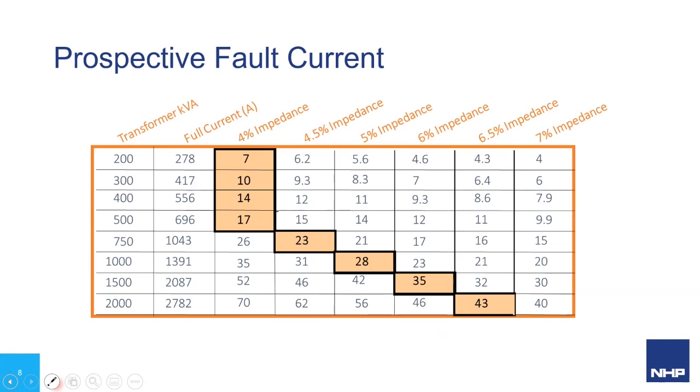The table shown here illustrates the possibilities of prospective fault current given an upstream low voltage transformer size, assuming an unlimited upstream supply and an internal build characteristic of the supply transformer.